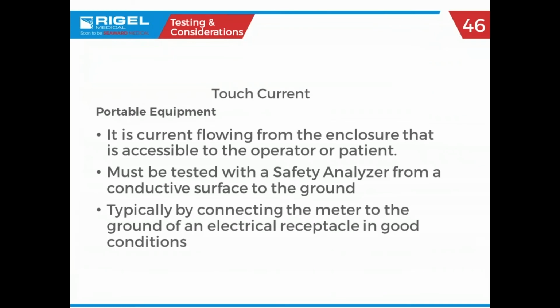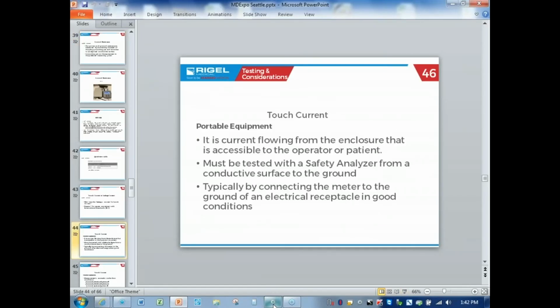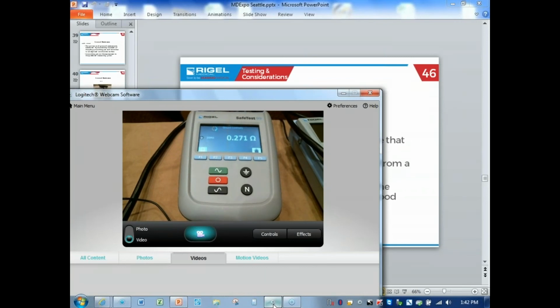We've already talked about it a couple times. Potential exists if there's a potential voltage sitting on a metal case. You touch it, you provide the path to ground. And we can do an example of that as well. So home, put power on. Just a little yellow warning that we have current. NFPA standard says to do this power on, power off. I'll just turn this on for now, just using this as a test mechanism. So there's my ground leakage.